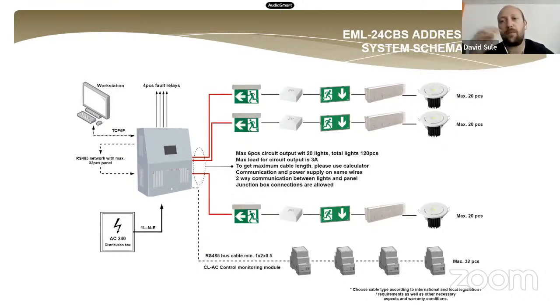So this panel does not turn on one circuit or all the circuits together. It sends the information to the address of the light, and we can make many separate groups of lights, and they can be controlled by any other panel's AC control unit command. So we can make a very big networked system from the panels, which can connect to each other over a TCP/IP network and an RS-485 network too.